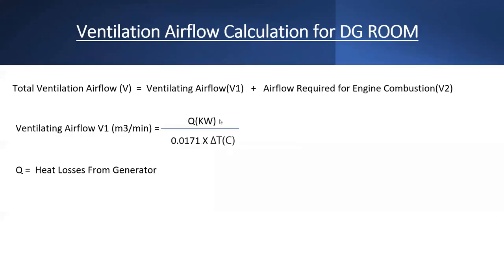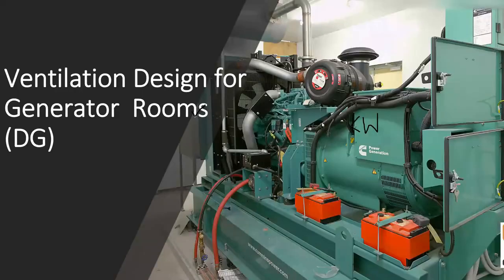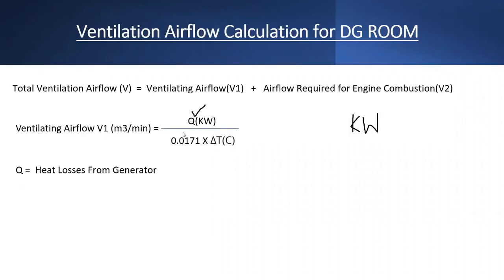So if we know Q and the temperature difference, we can calculate how much ventilation airflow is required in the DG room. The Q here is the heat losses from the generator — it is not the electrical kilowatt rating of the generator. Q is the heat dissipation: the heat radiated from the radiator and from the engine into the room space. That is the heat dissipation we need to remove.